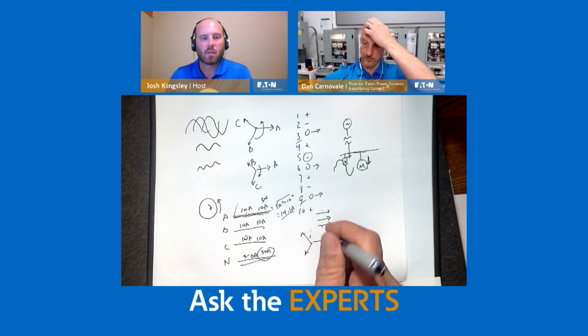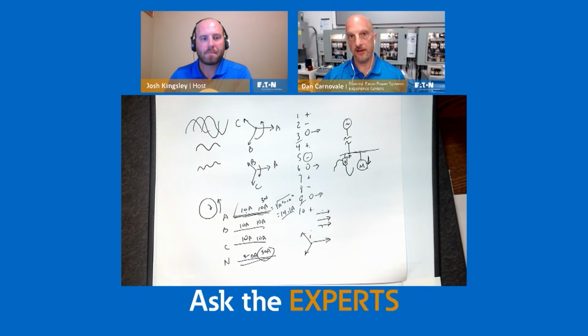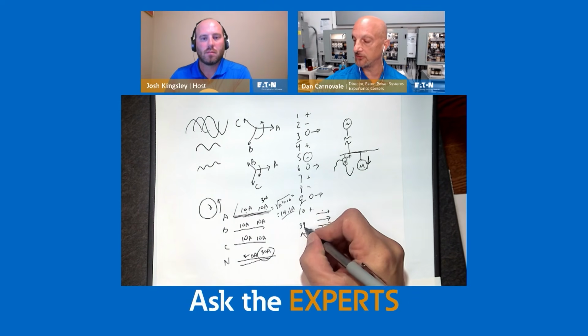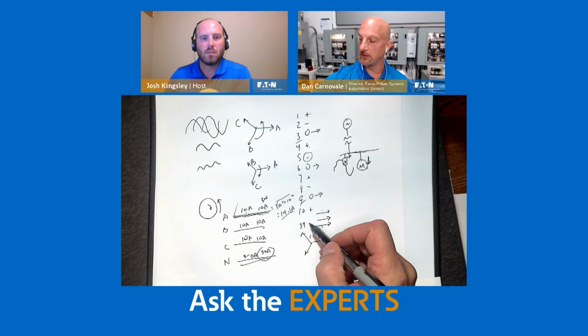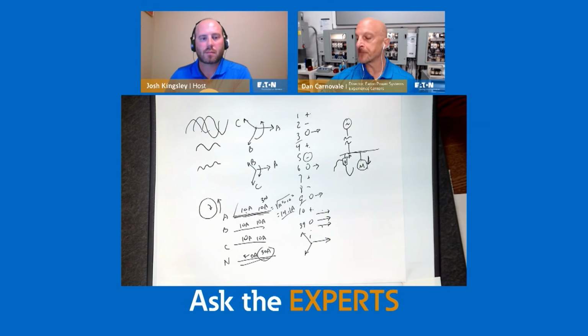So zero sequence harmonics add up on the neutrals. And we talked about it earlier with the question about the medium voltage and 480 volt systems, where maybe high frequency ones, I mentioned the 39th harmonic. So if you keep expanding this list out, when you get to the 39th, it's going to be zero sequence. Positive sequence harmonics just add extra current to the system. It's like adding extra load on your wires, and it can overheat things. Negative sequence tends to make things want to go backwards. Zero sequence tends to add up again in a way.